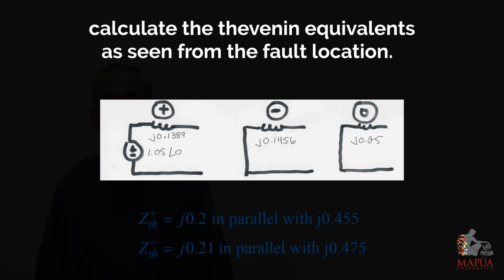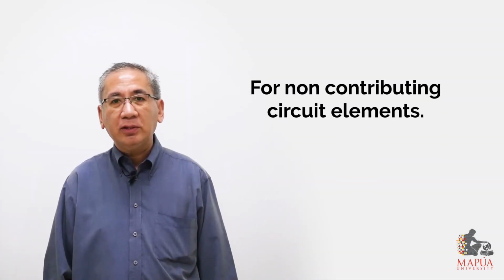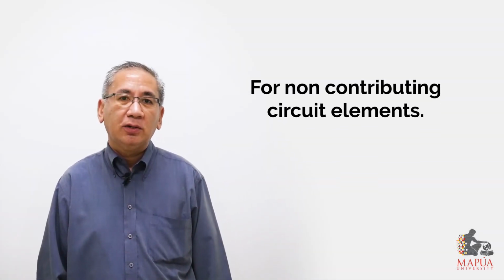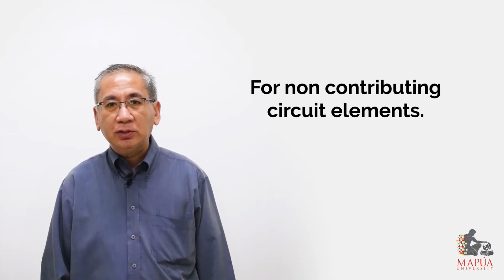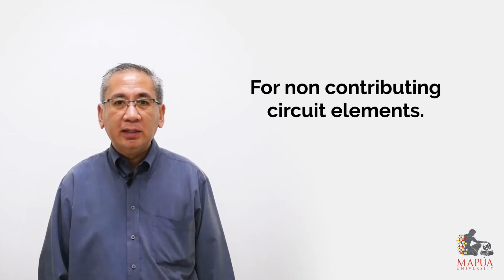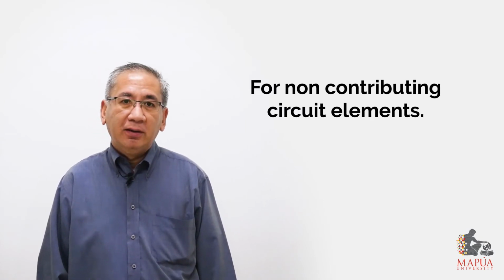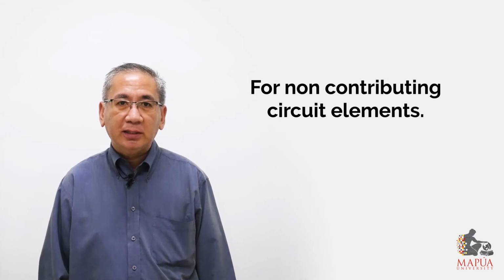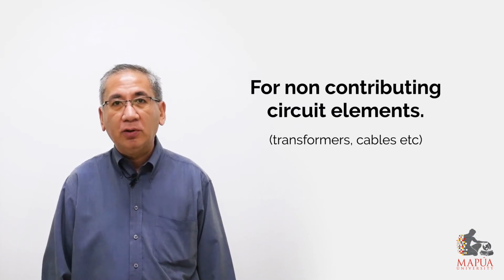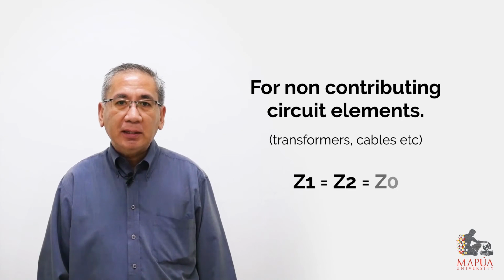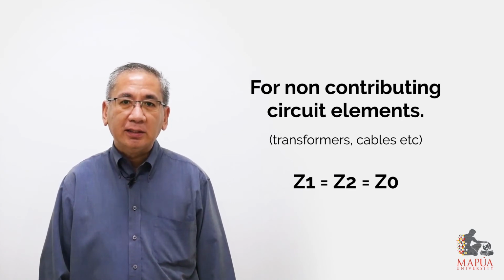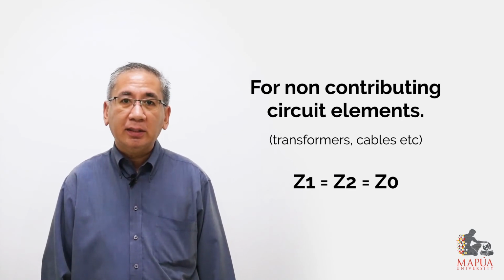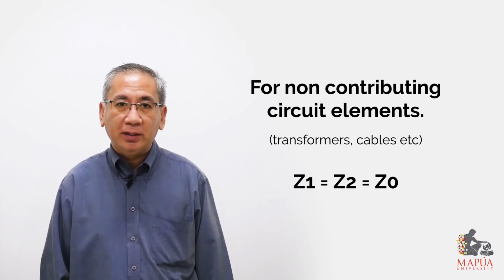Now, for system impedances, what should be the expected values of the sequence impedances? First, for non-contributing circuit elements such as transformers, cables, etc., the positive, negative, and zero sequence impedances are the same. They are equal.